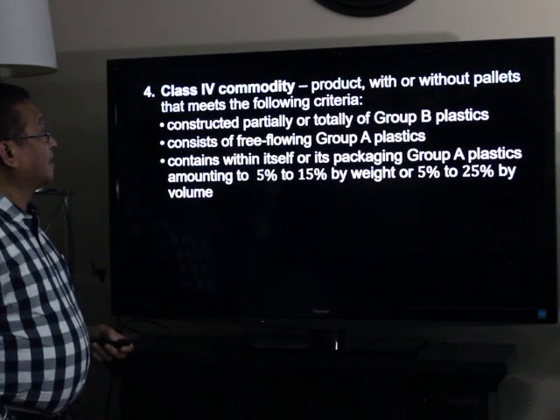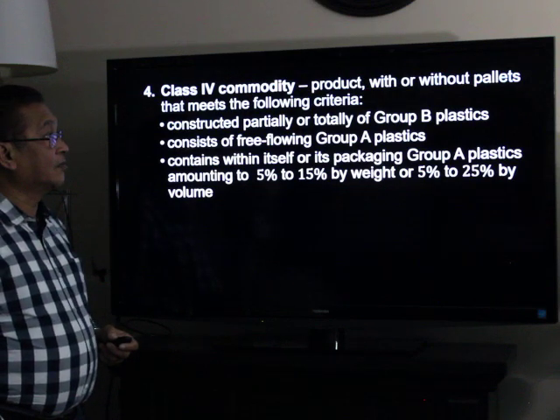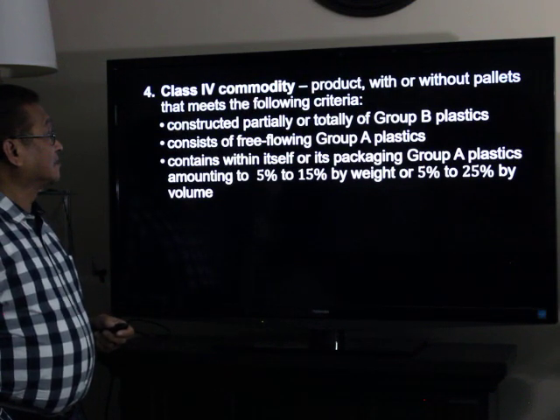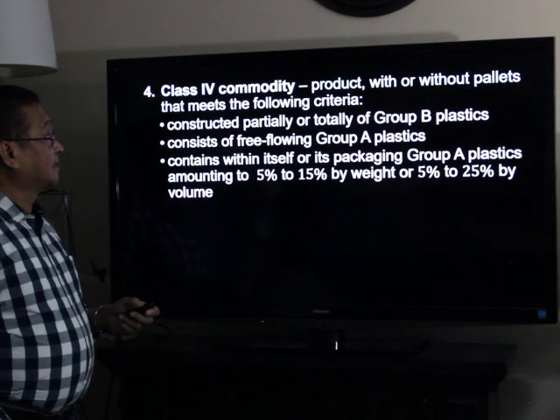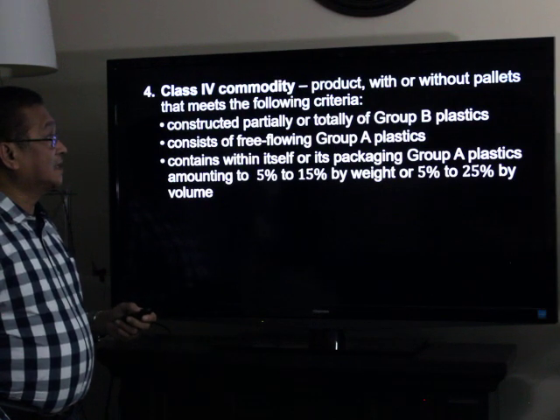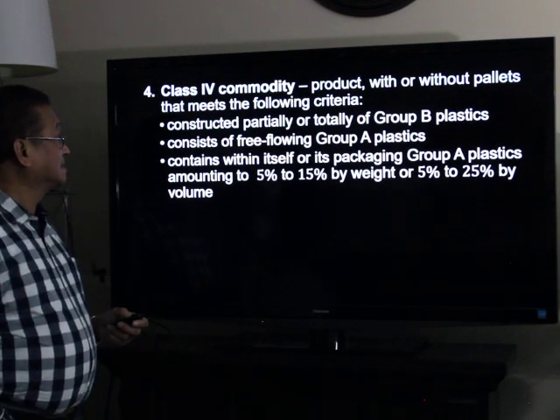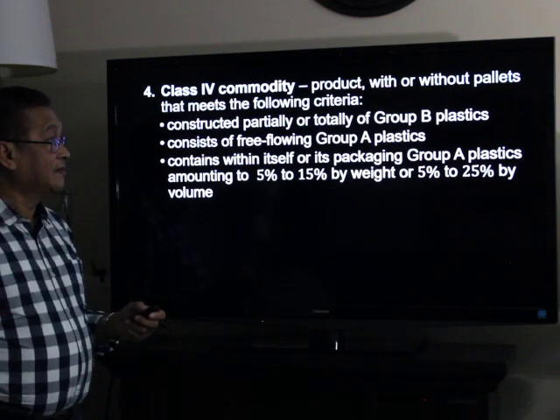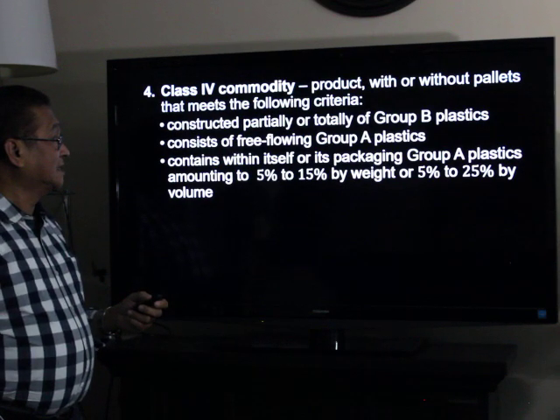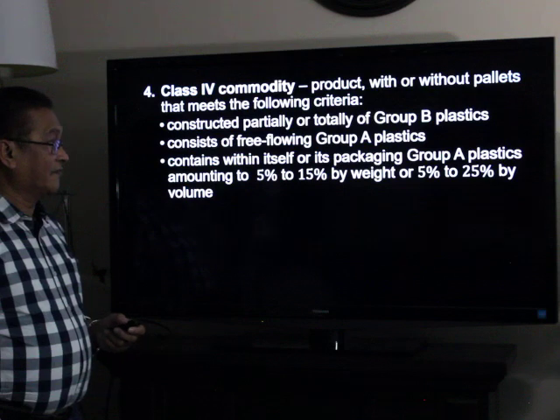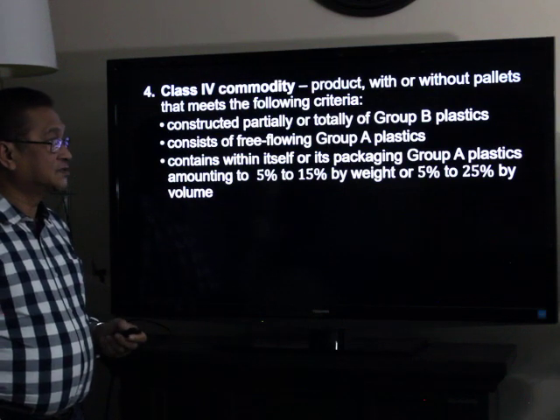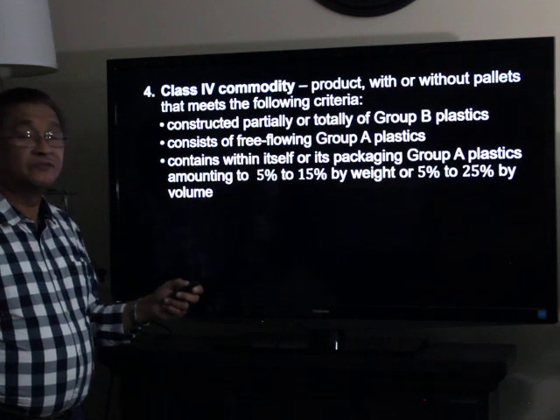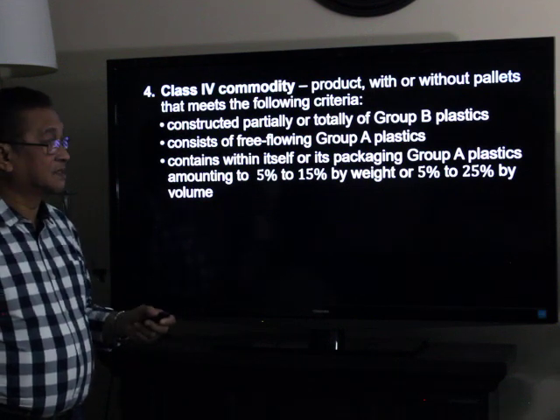Class four commodity: a product with or without pallets that meets the following criteria — constructed partially or totally of Group B plastics, consists of free-flowing Group A plastics, and contains within itself or in its packaging Group A plastics amounting to five to fifteen percent by weight or five to twenty-five percent by volume.